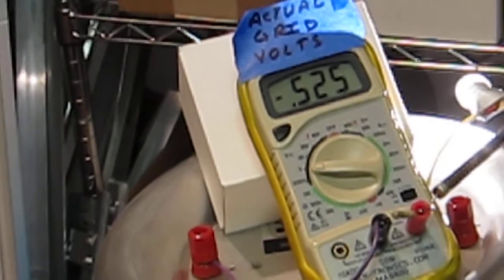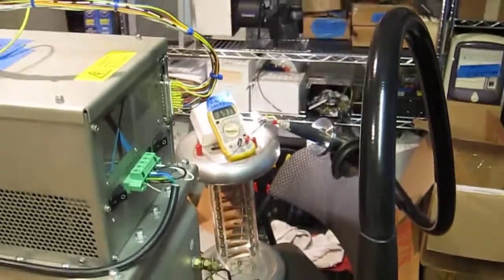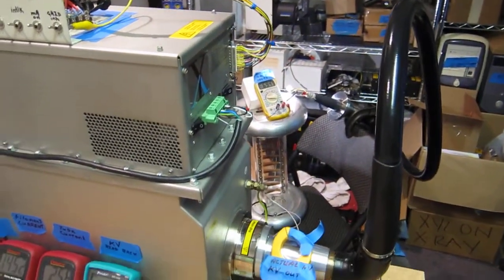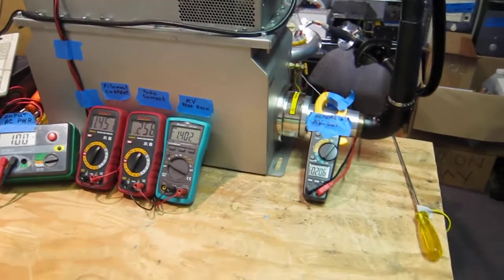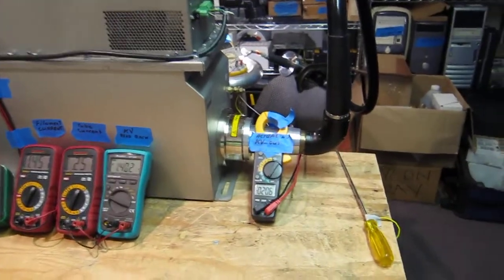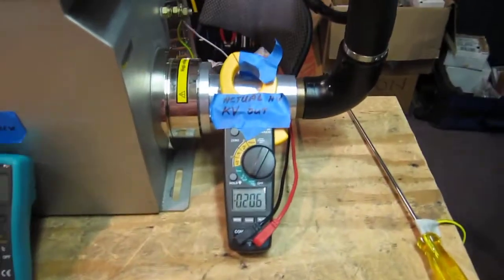So basically I'm proving that all of these circuits are functional, but unfortunately, because of this installation and the fact that I'm not using an X-ray tube, I cannot run the high voltage all the way to 160 kilovolts. I'm afraid it'll arc over, and it's possible that one arc could damage the high voltage power supply.